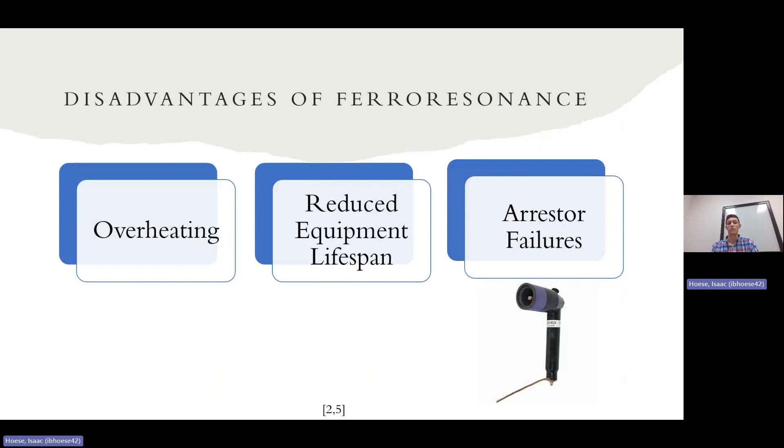And then arrestor failures. Obviously, the arrestors on transformers are to combat lightning. So lightning has over voltage and over current, which ferroresonance meets both of those criteria. So the arrestors could fail thinking that it was a lightning strike. And the transformer itself, it could explode because of the oil inside the transformer heating up. So there's lots of bad reasons that ferroresonance can affect your system.